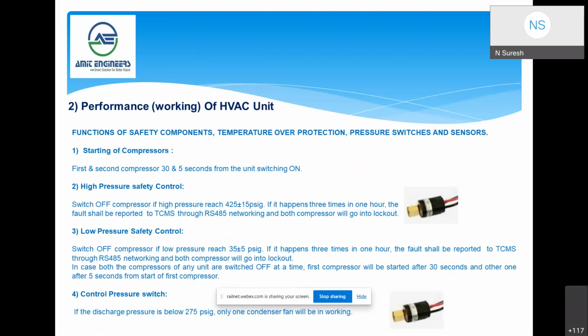Normally, whenever the system is switched on, it will take 35 seconds for the first and second compressors to start after the unit is switched on. There is a high pressure safety cutout switch, a mechanical switch. In case the pressure exceeds 425 psig plus or minus 15, it will switch off the compressor, and a signal is provided to the microprocessor as well as to the TCMS.